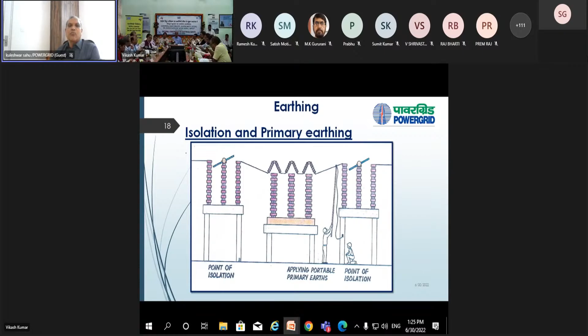This is a sample where two isolators and a breaker are there. So when we want to go for testing of the breaker, first we have to open the breaker, then after that open the isolator. Then if the system has a permit, if an earth switch is there, we close the earth switch. And if additional induction is there, then additional portable earthing is also applied. Next.